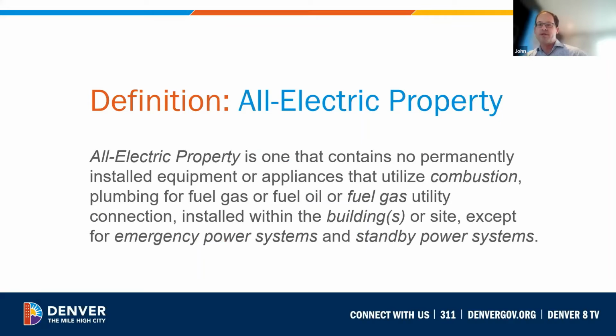New to the 2022 Denver Energy Code is the definition of an all-electric property. This is used in several places to facilitate easier compliance for all-electric properties. An all-electric property is one that contains no permanently installed equipment or appliances that utilize combustion, plumbing for fuel gas or fuel oil, or fuel gas utility connection installed within the buildings or site, except for emergency power systems and standby power systems. Emergency power systems and standby power systems are defined in the code, where the interruption of the primary power could result in the loss of human life, serious injuries, or could create hazards or hamper rescue or firefighting operations.